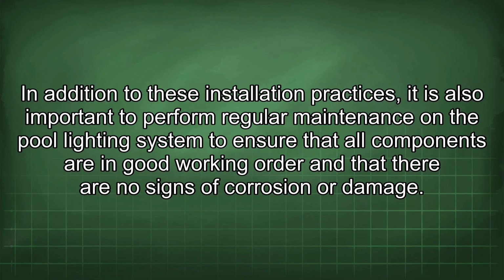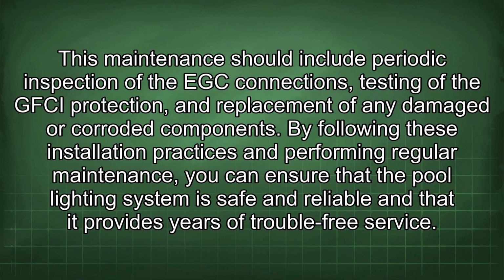In addition to these installation practices, it is also important to perform regular maintenance on the pool lighting system to ensure that all components are in good working order and that there are no signs of corrosion or damage. This maintenance should include periodic inspection of the EGC connections, testing of the GFCI protection, and replacement of any damaged or corroded components. By following these installation practices and performing regular maintenance, you can ensure that the pool lighting system is safe and reliable and that it provides years of trouble-free service.